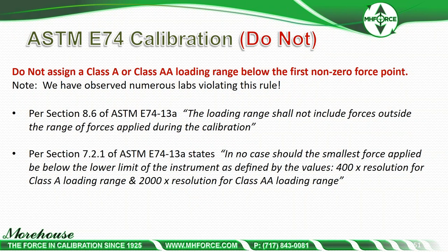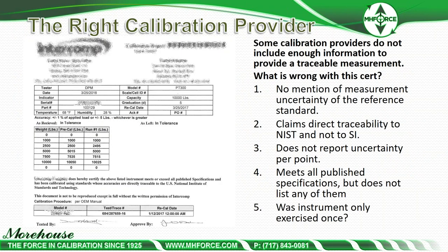Some calibration providers do not include enough information to provide traceable measurements. Looking at this cert: there's no mention of measurement uncertainty of the reference standard anywhere; it claims to be 'directly traceable to NIST' rather than to SI; it does not report uncertainty per point as required by ILAC P14 for accredited calibrations; and it makes the statement 'meets all published specifications' without listing any of them. There are also questions about whether the instrument was properly exercised.